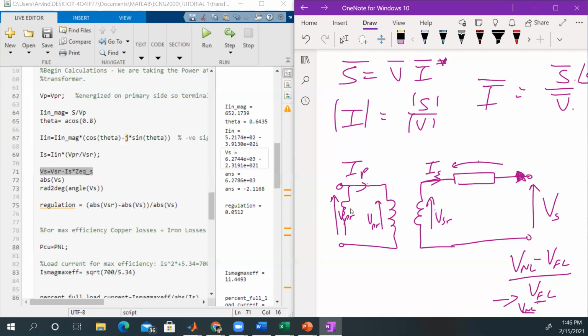But then there is this core loss in there, which is also taking some current, which means the current that comes from the terminal is actually more than the rated current. So it doesn't make sense mathematically. It is not extremely consistent with theory. What you see in practice, and standards for transformers have been changing over time.